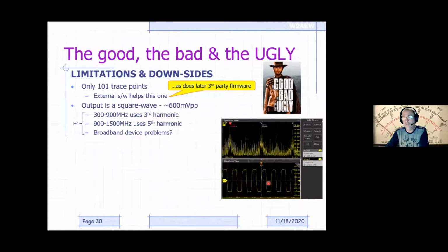In fact, this display is a 200 megahertz square wave. This is the exact same output that you'd get if you're making measurements at 200 meg or 600 meg or 1 gigahertz. It's the exact same output, okay? Because we're just using the different harmonics of that same signal. So you have to think about what kind of device you're measuring, and will it have a problem with the fact that the signal is a square wave and not a sine wave? Will it have a problem with the fact that it's got all this higher order harmonic energy in it?